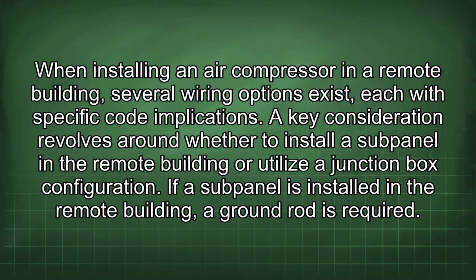When installing an air compressor in a remote building, several wiring options exist, each with specific code implications. A key consideration revolves around whether to install a subpanel in the remote building or utilize a junction box configuration. If a subpanel is installed in the remote building, a ground rod is required.